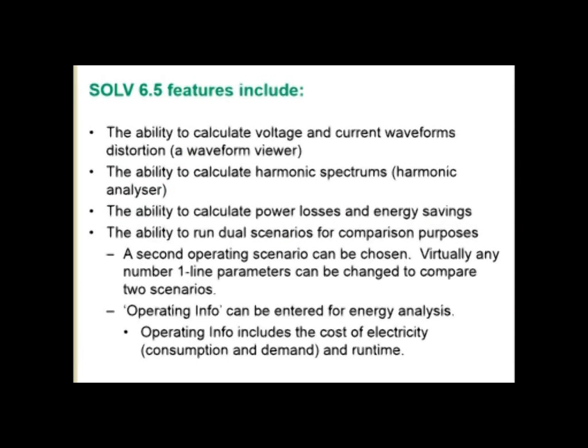SOLV 6.5, as its predecessors, is computer simulation software designed for harmonic analysis with adjustable speed drive applications. Main features include the ability to simulate voltage and current waveform distortion, ability to calculate harmonic spectrums, ability to calculate power losses and energy savings. Also the ability to run dual scenarios, which was a new feature introduced last year.